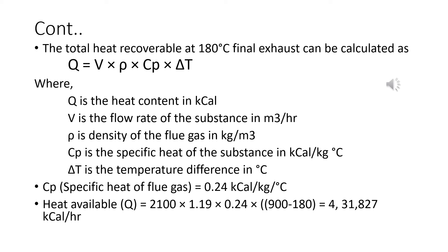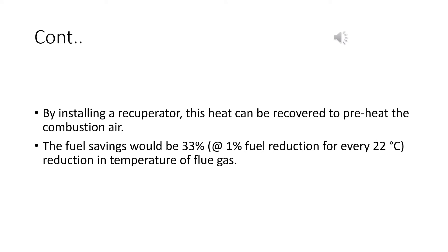Heat available Q = 2100 × 1.19 × 0.24 × (900 − 180), which equals 431,827 kilocalories per hour.